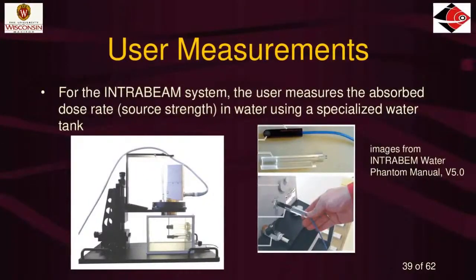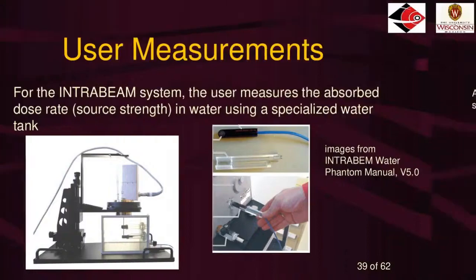For the Zeiss IntraBeam system, they don't include a well chamber. You have the option to buy a water tank — most users do — and place a parallel plate chamber inside to measure dose rate in water using the formalism I showed earlier. This is a very different way to measure the output of these sources. The water tank holds the sources and chambers very precisely because the chamber must be positioned very accurately so close to the source.